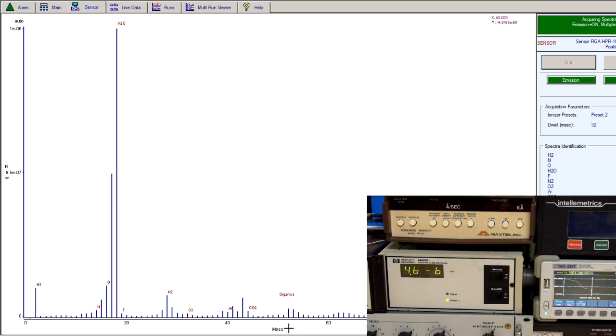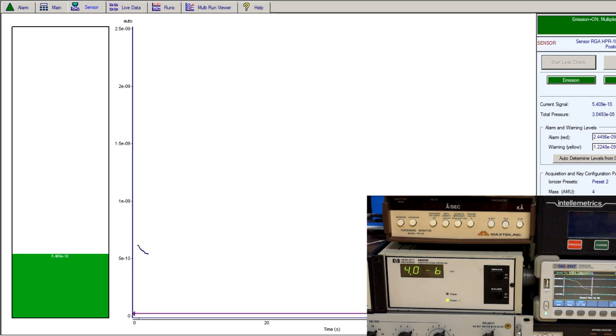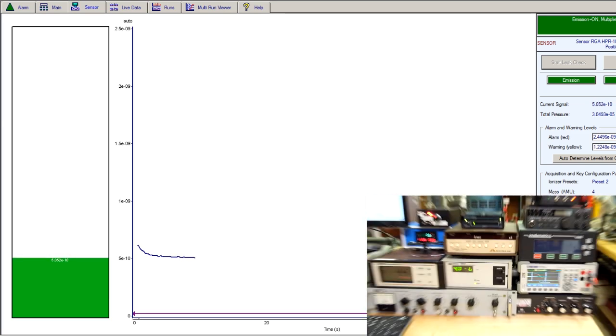I'm going to stop this — I didn't really see anything too alarming down in the lower AMUs to explain the pressure fluctuations and that interesting pumping curve, because there's not a whole lot of backstream oil and everything else looks okay. So we're going to do a helium leak check, and hopefully that'll find the problem. I'm into the leak checking mode — we're looking for helium at atomic mass 4. I'll keep the multiplier on for maximum sensitivity, and go ahead and start the leak check. We have audio, so I can walk around the chamber and use a helium wand.